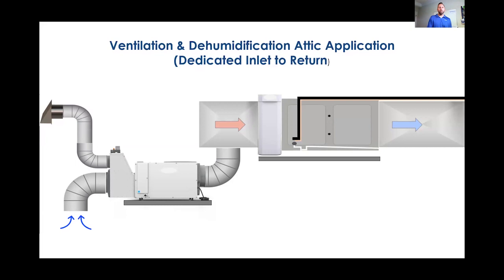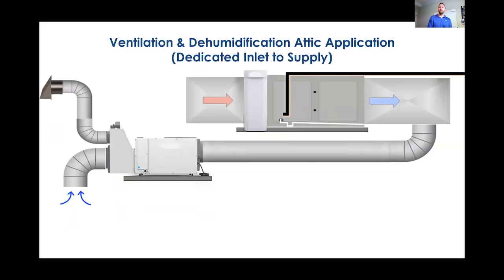Those attic and those crawl space applications, no problem at all. We can do the same thing whether you're in that return or in that supply. So again, what we're doing here is we're bringing that fresh outdoor air that might be humid, that might have a lot of moisture content. We're driving it through the dehumidifier. If it needs to be dehumidified, it will dehumidify it. If it doesn't, it just simply shuts the compressor off and you've got a great powered ventilation system.